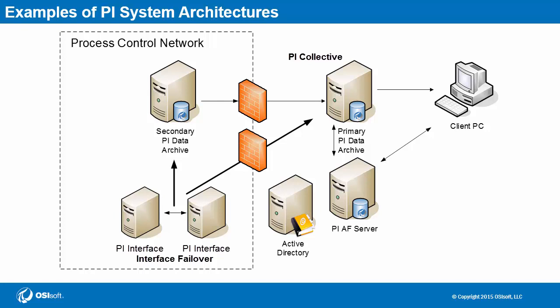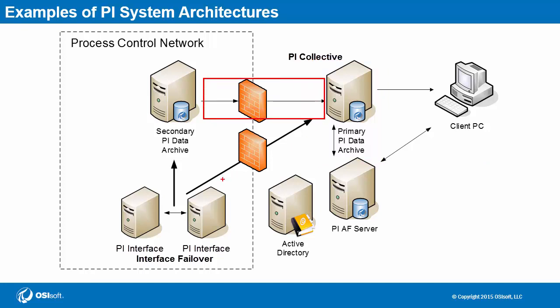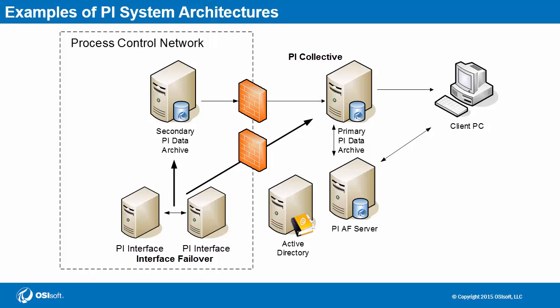In this next example we take one of the PI collective members out of the sensitive process control network and into the corporate network. This could be for a number of reasons. For example, if the amount of network traffic coming from end users is too much for the process control network to handle, you may consider taking a PI data archive out like here. This can immediately provide better quality of service for the users, although you will have to take into consideration a different type of traffic between the firewalls — namely PI collective synchronization and n-way buffering — but this might be worth it depending on the differences in network load with this architecture.